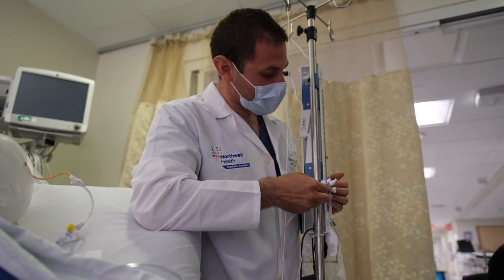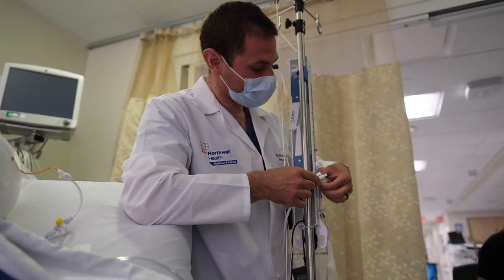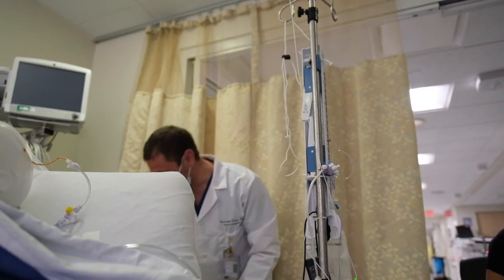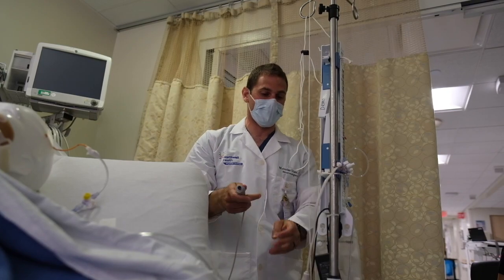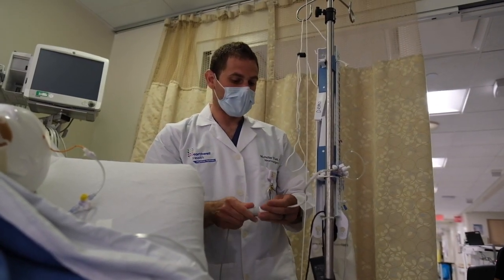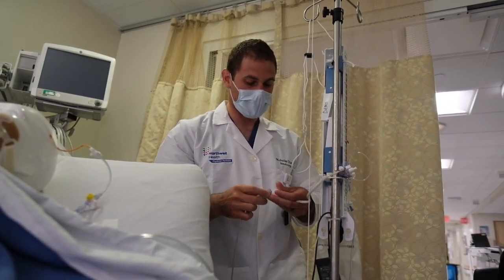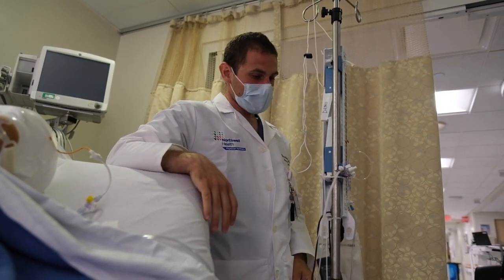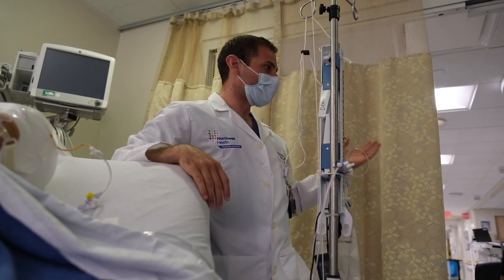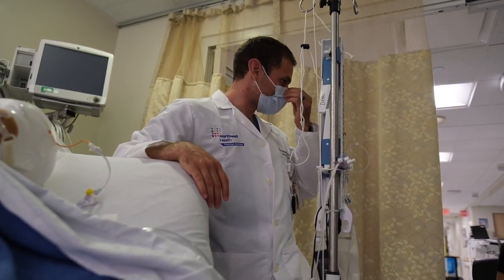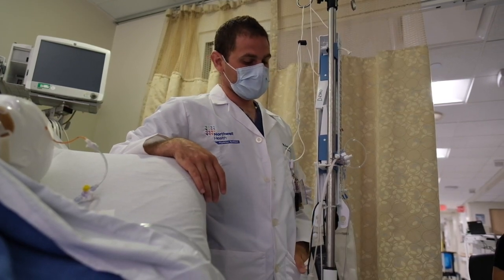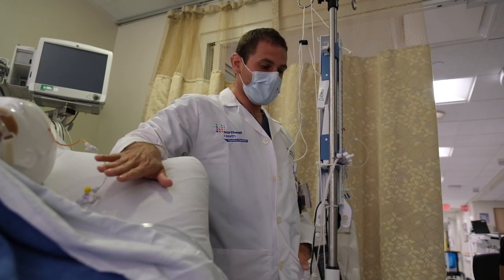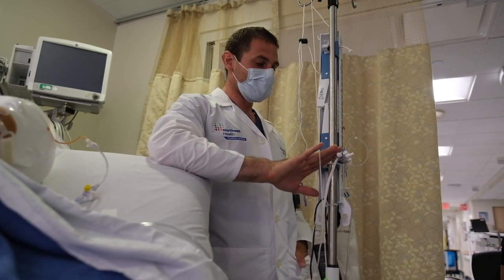So you simply just attach it, okay? And that's it. You have the rest of your transducer here. You connect it. And then after you zero it and do everything else you normally do, probably better than I do, you'll get a waveform. It'll look similar to your pulse ox and arterial waveforms. So that's the components of it. That's how to set up the ICP.